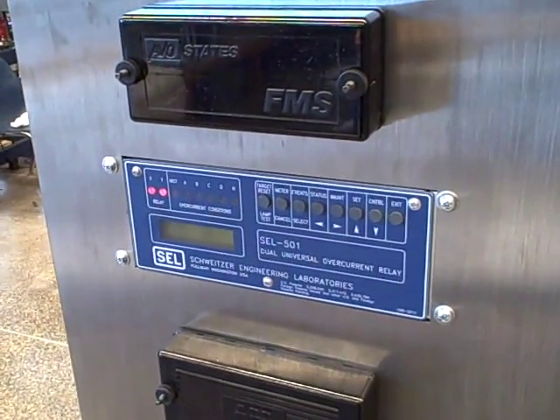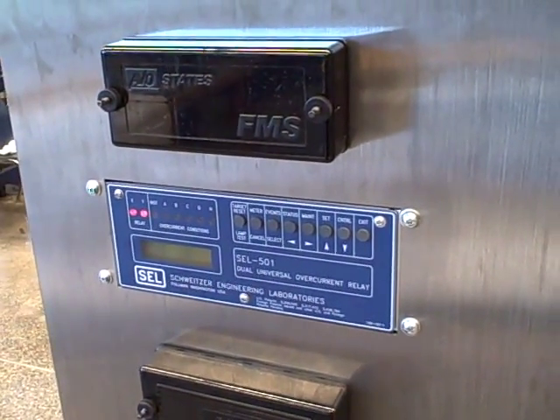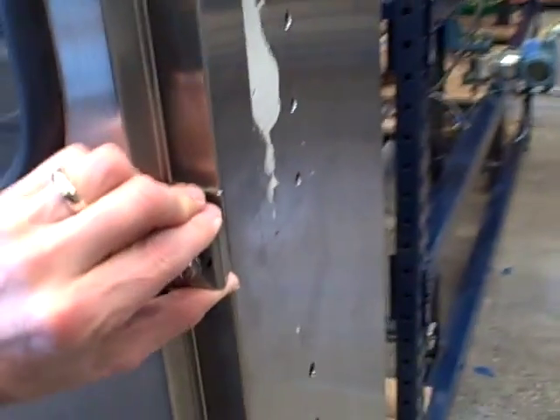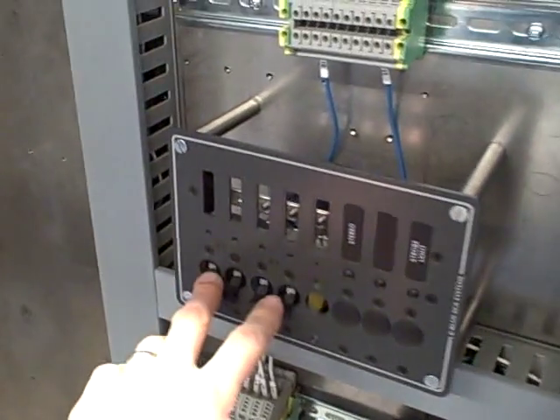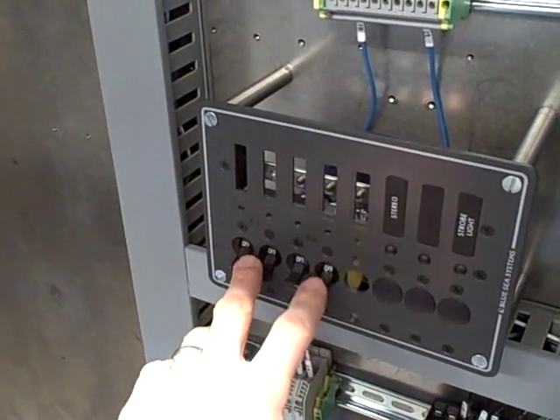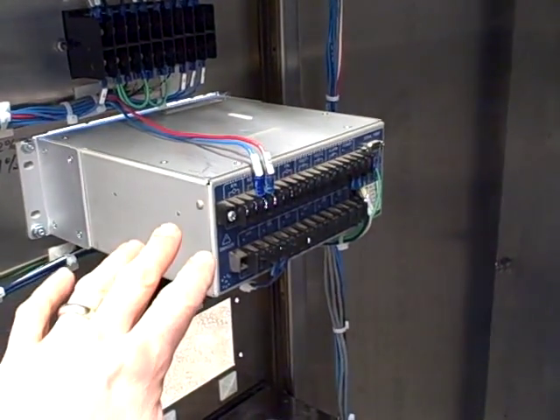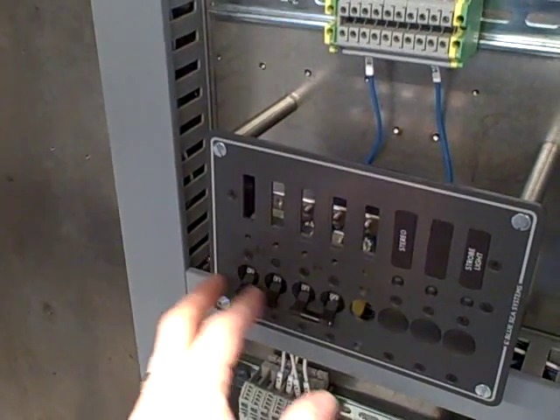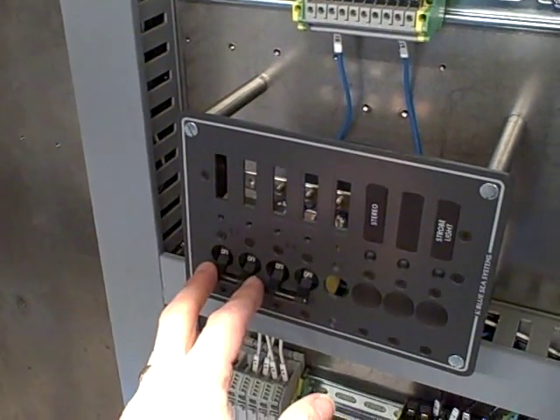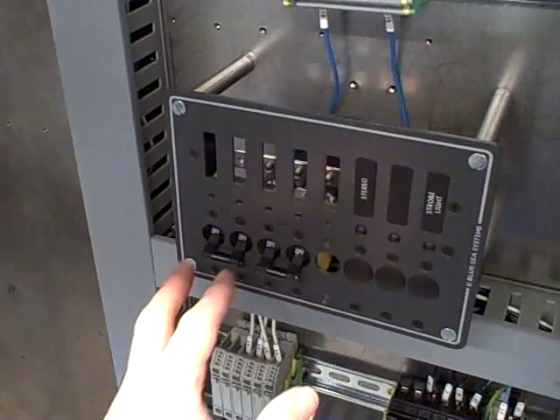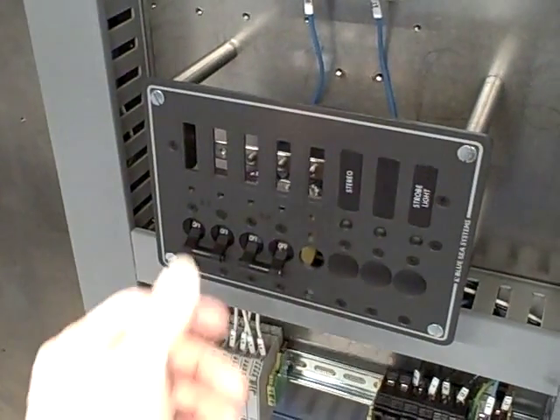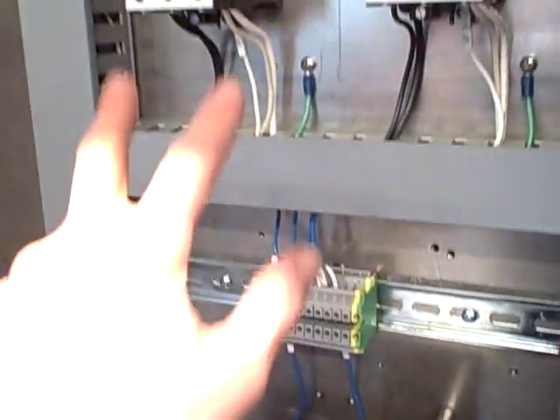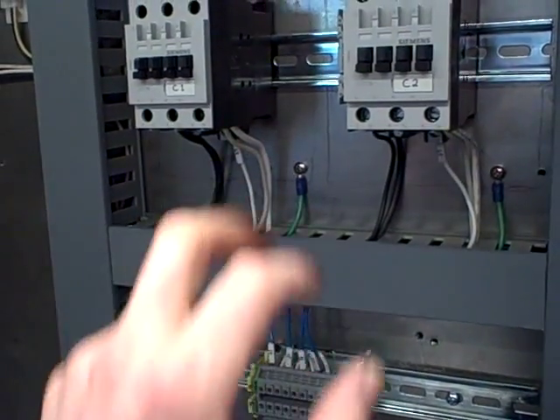We don't have any large circuit breakers to trip, so in this system we have small circuit breakers with built-in trip coils that are electronically trippable. When a contact closes on the protective relay, it sends DC power to the breaker to cause it to trip. This breaker doesn't have current carrying capacity large enough to handle the loads we expect, so we're using these breakers to drive contactors which actually conduct the load power.